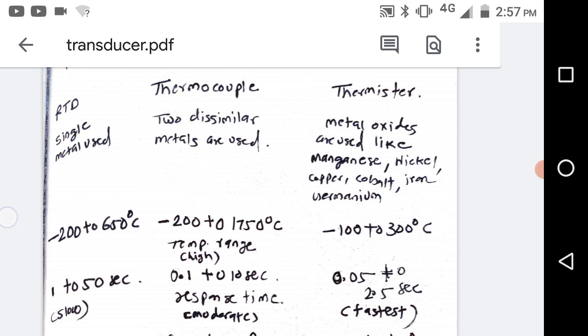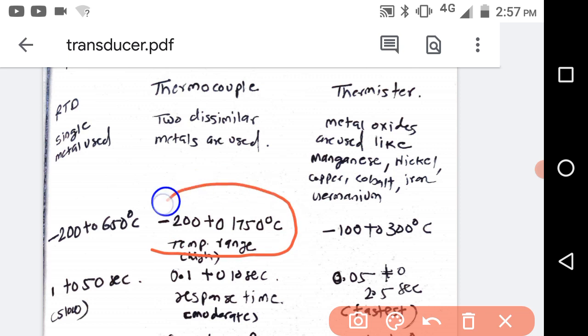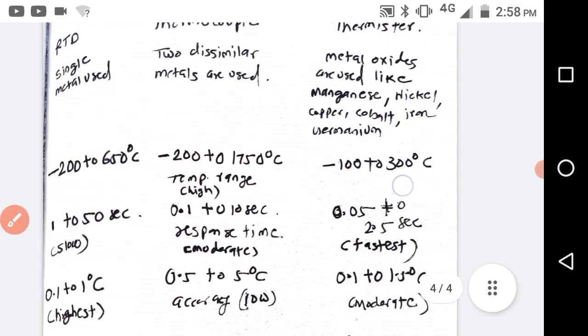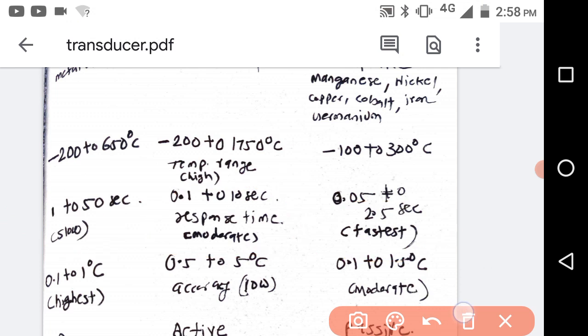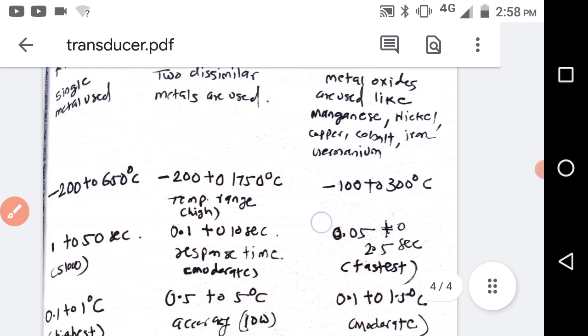So let us see how much temperature range is covered by these three. So here you can see the thermocouple can measure the highest temperature range in comparison, then RTD and then thermistor. So thermistor is lowest in case of the temperature range. Now let us see the response time. Response time of thermistor is lowest because it converts the temperature to the electrical energy in maximum 2.5 second, while the thermocouple will convert it in 10 second and RTD in 50 second.